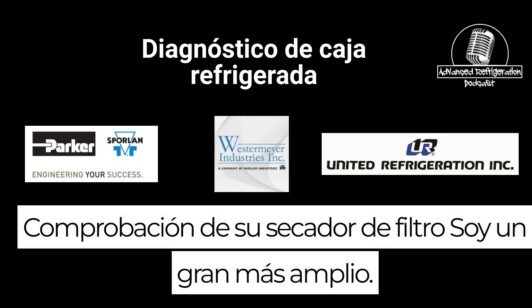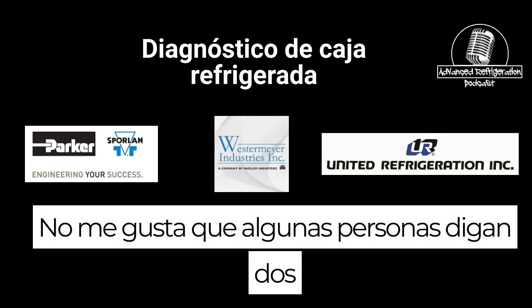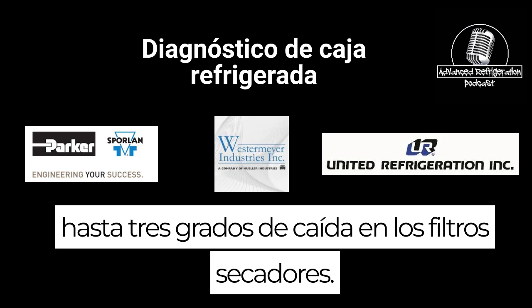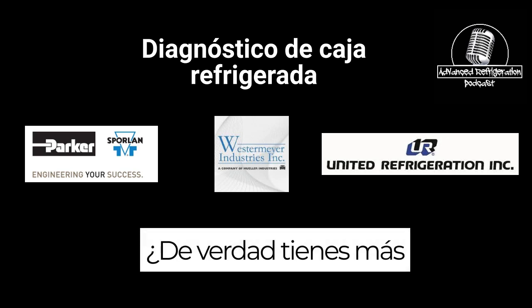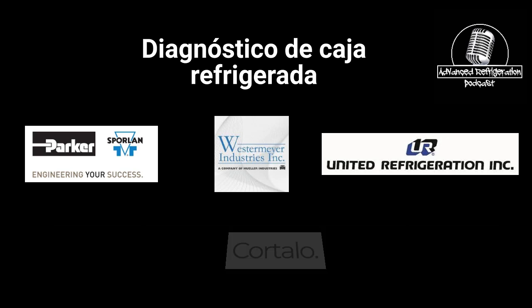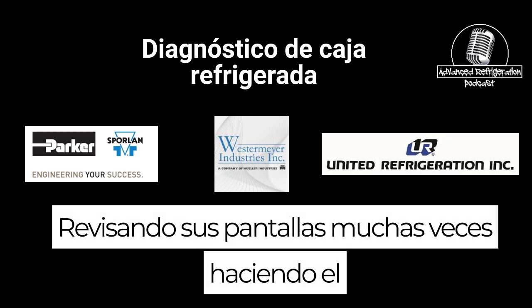Checking your filter dryer. I'm a big proponent. Some people say 2 to 3 degrees drop across filter dryers. If you really have any more than a degree across that dryer, cut it out. Checking your screens.